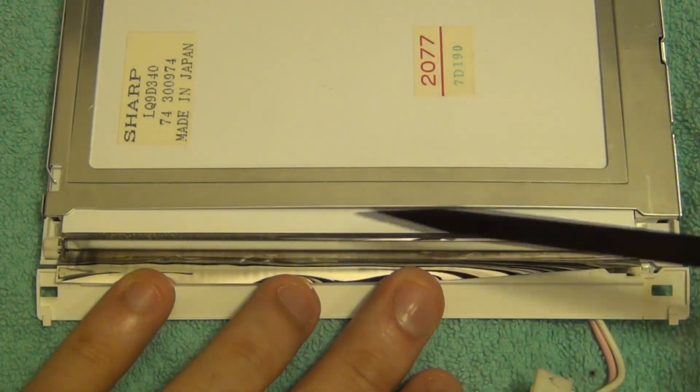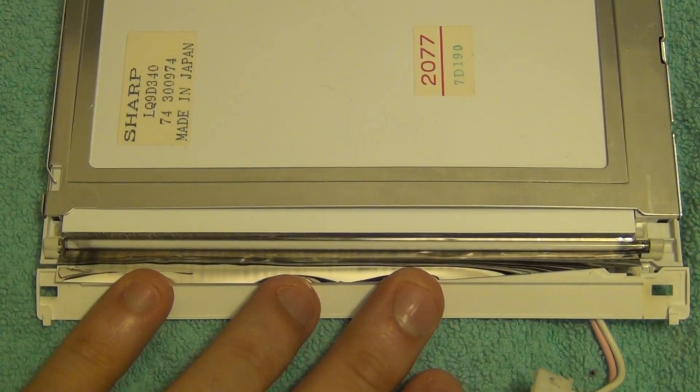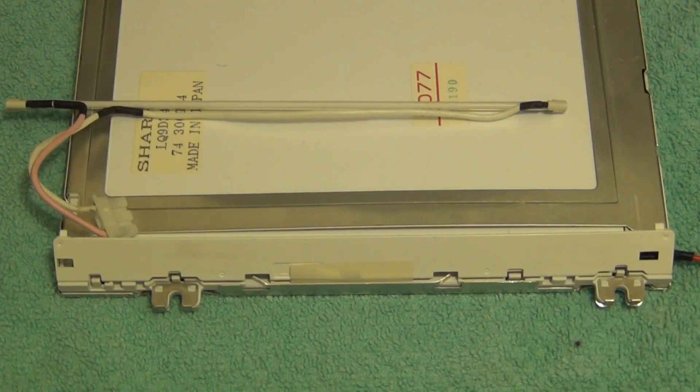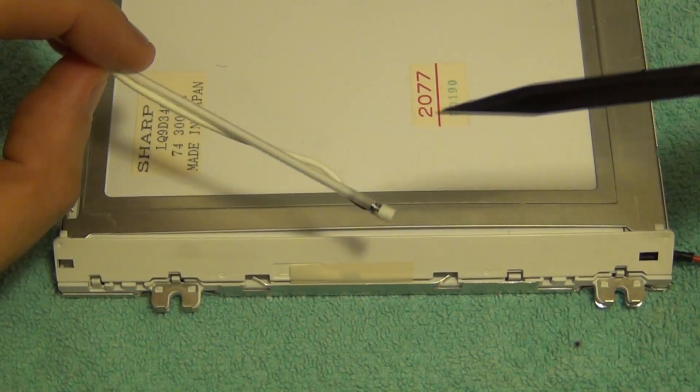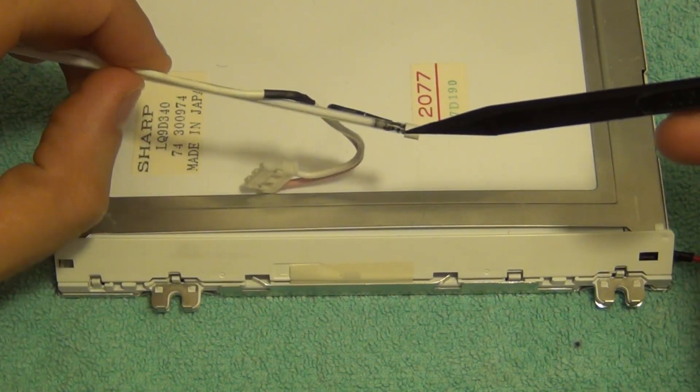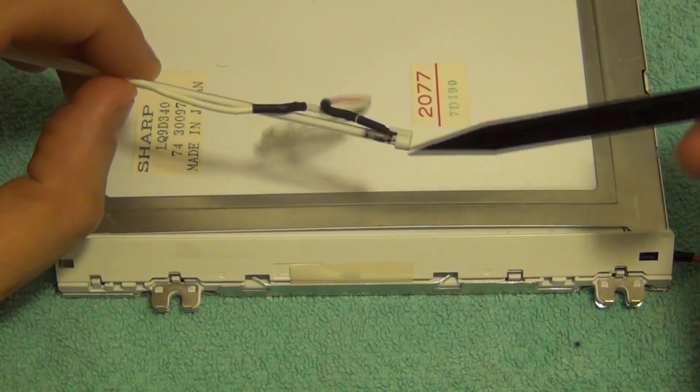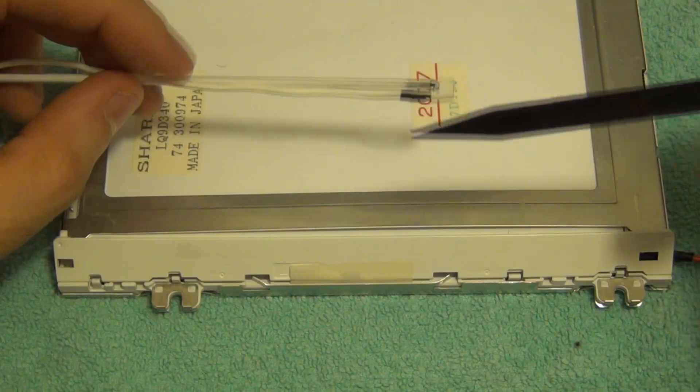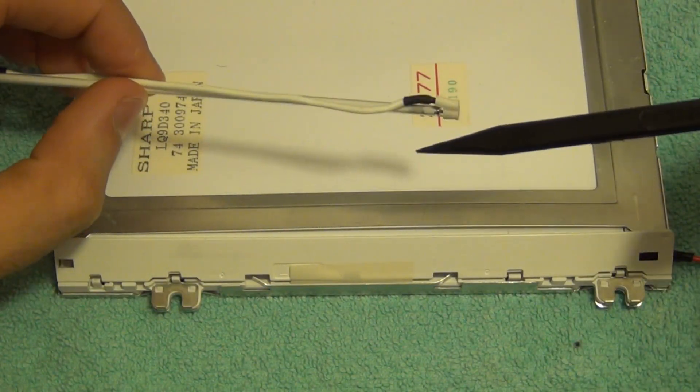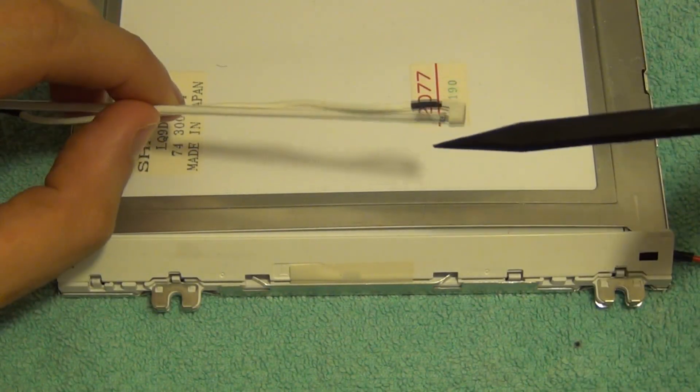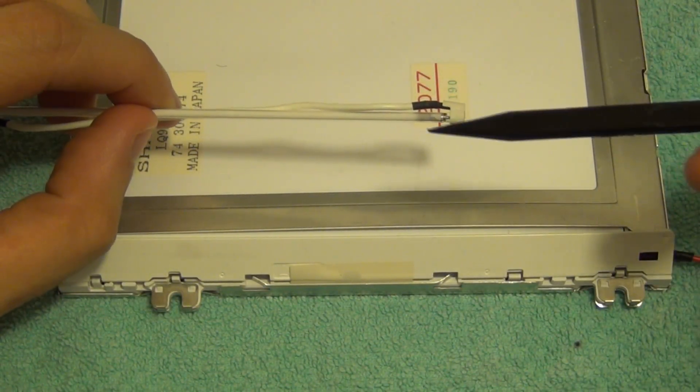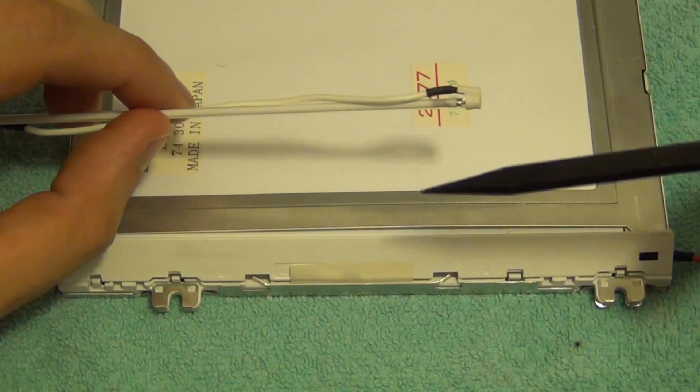Took the tube out and you can clearly see the black regions at the end which is generally caused by the sputtering of the electrodes from high energy impact of the electrons from the tube when it's running. This happens as they age.